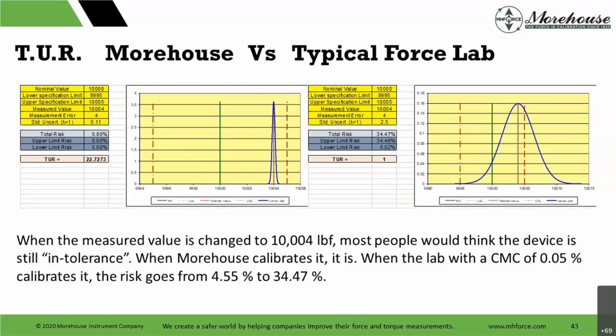Now, ILAC G8 says you can fail when it's the tolerance plus the uncertainty that it's out, but that's all of your graph being out. So again, it comes down to risk, and we're going to go over risk and why that's important. But in this scenario, the risk goes from 4.55 to 34.47. And what that's saying is if I use this instrument and I calibrate other instruments, I have a 34.47% chance that my device right now is out of tolerance.